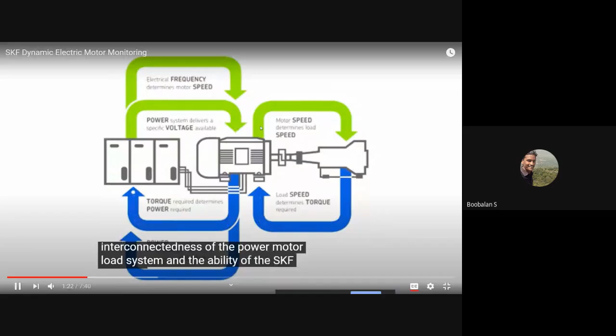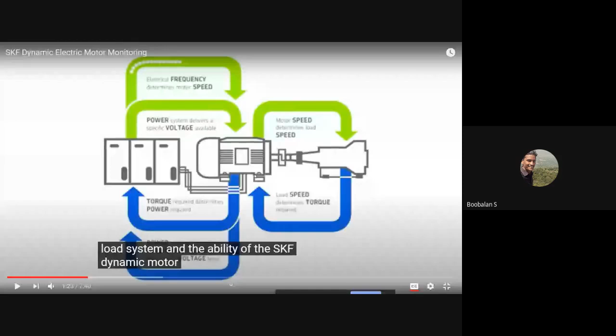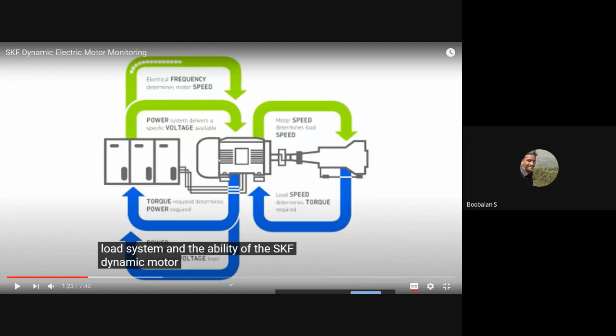Now there is a feedback coming from this load torque. There is a load torque sensor attached with this mechanical driving system, and it's giving the feedback to the motor. Now there is one more torque, besides the load torque, that's called motor torque, and both are compared in my controller, that's called VFD. Now it's going to deliver a power supply to that particular motor according to this load torque, right?